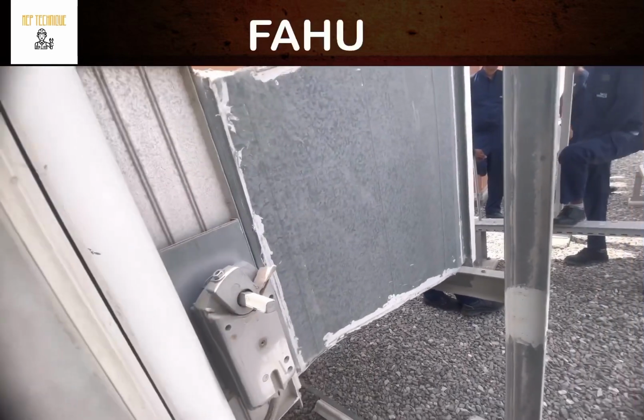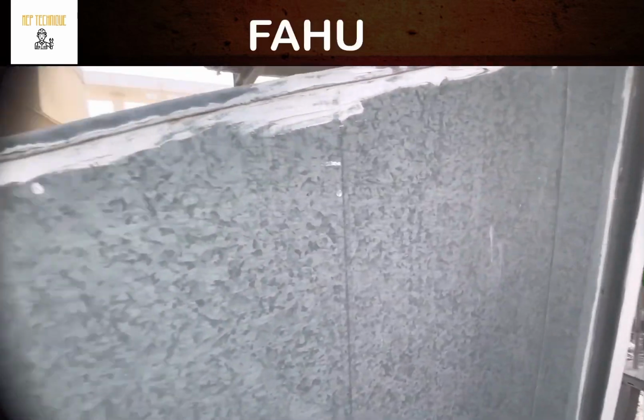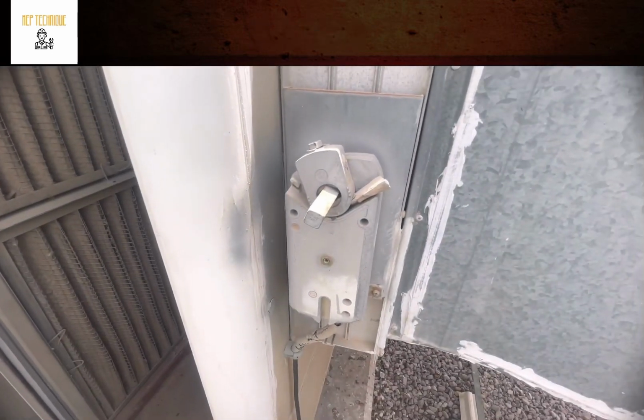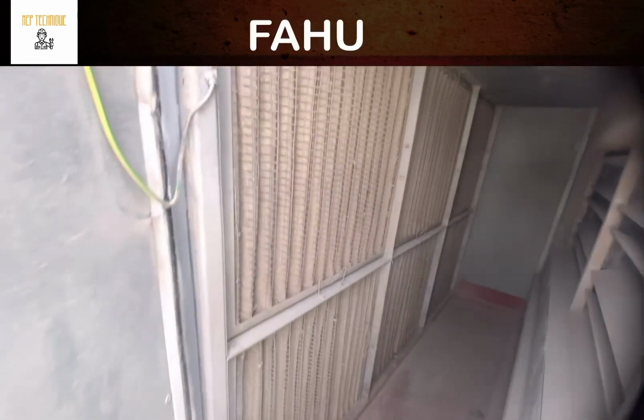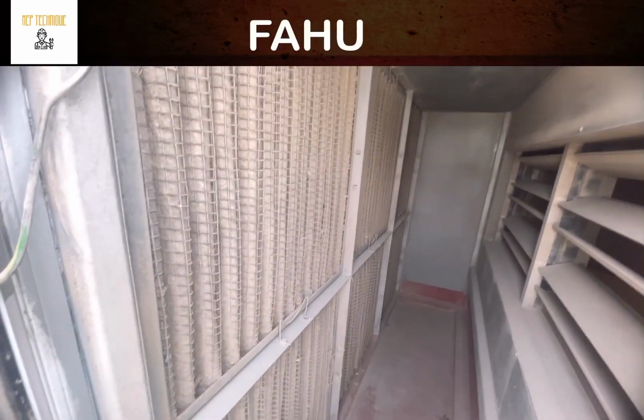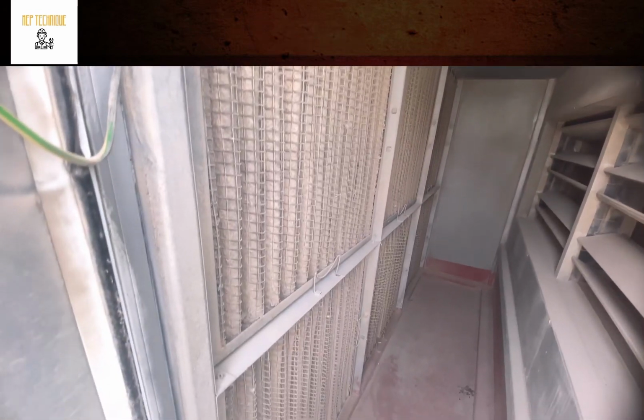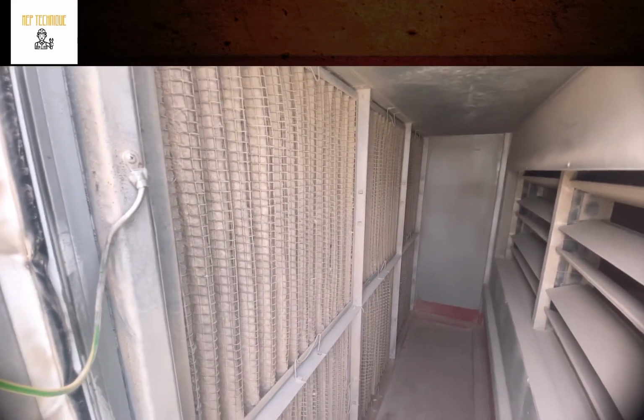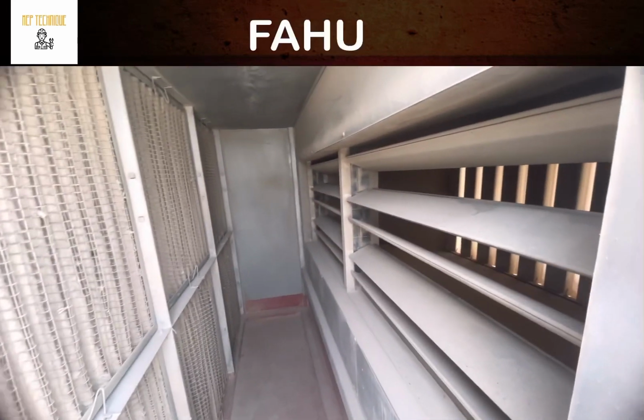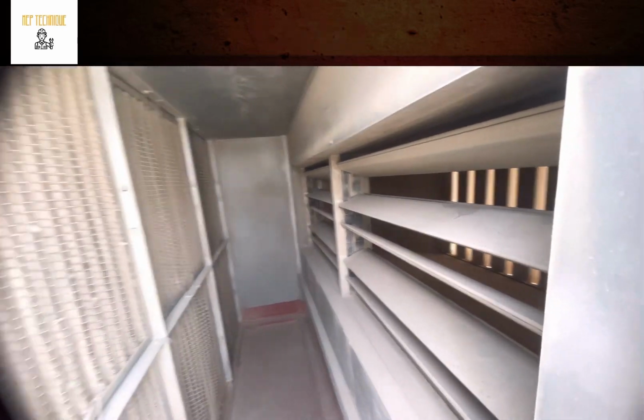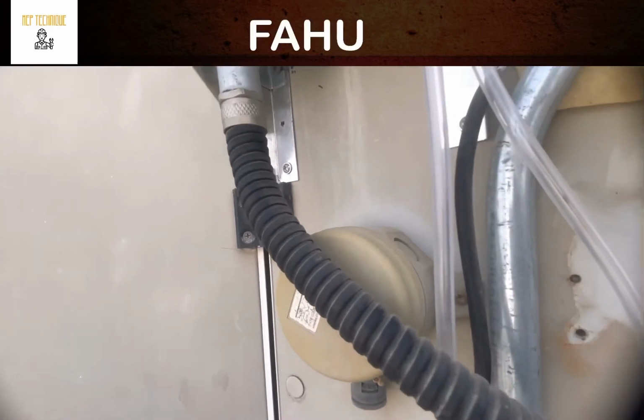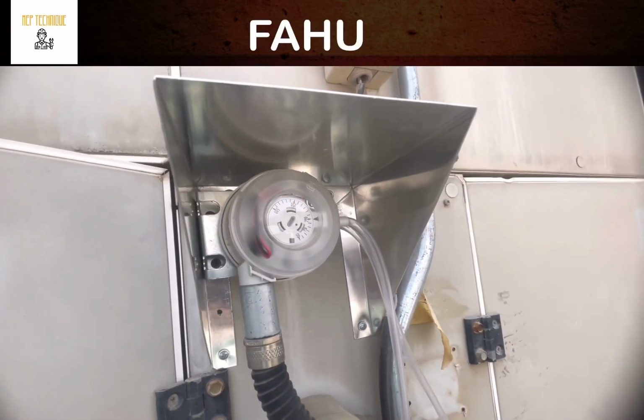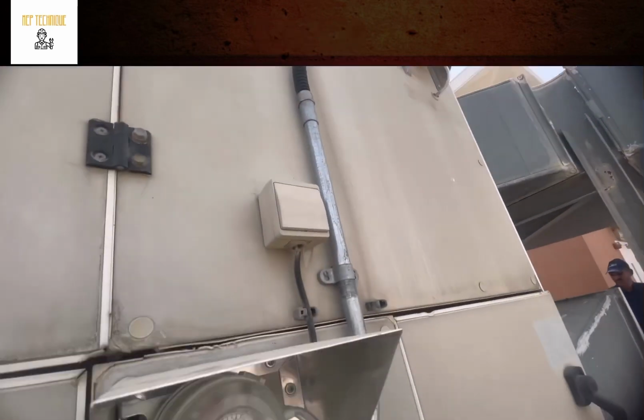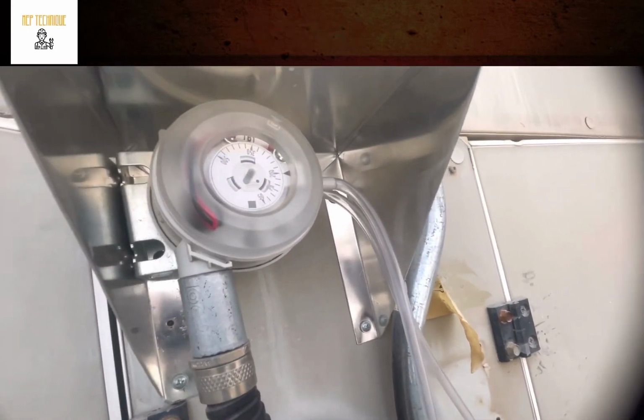So this is the duct connected from outside. Okay, so this is a VCD, volume control damper, and this is our pre-filter. The efficiency of the pre-filter is 30%. That means the pre-filter can arrest 30% of the dust where the air comes from outside. Then after that, this is the DPS. There are two DPS, one here and another one there. DPS means differential pressure switch.